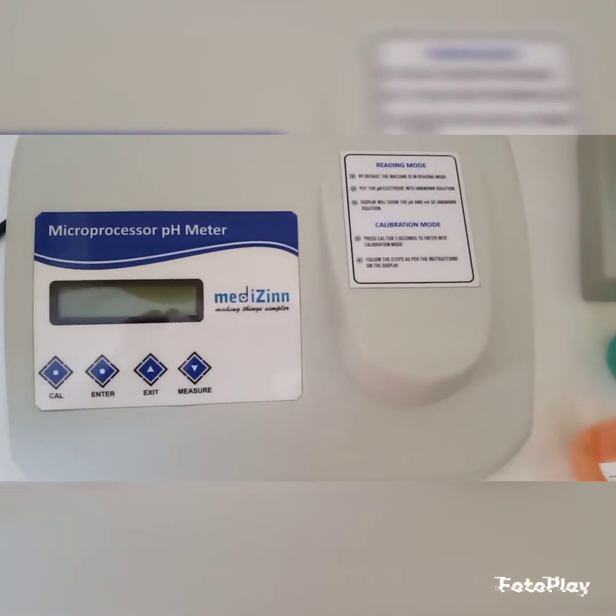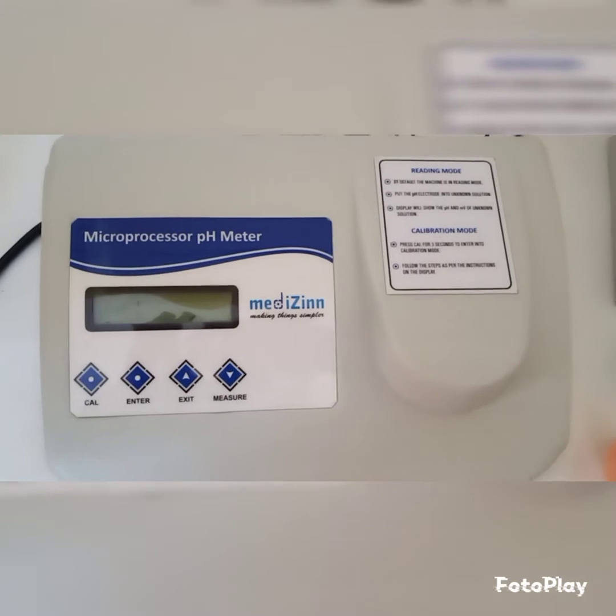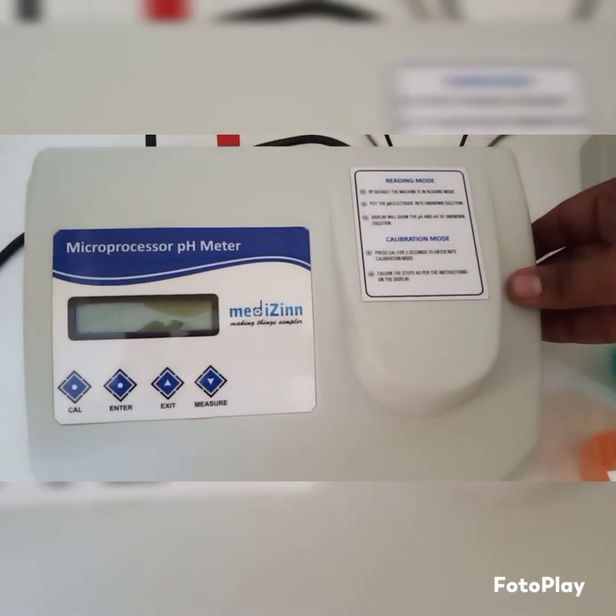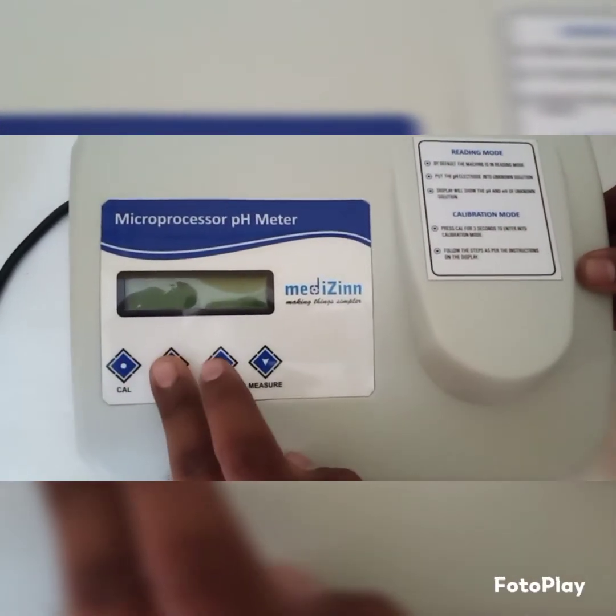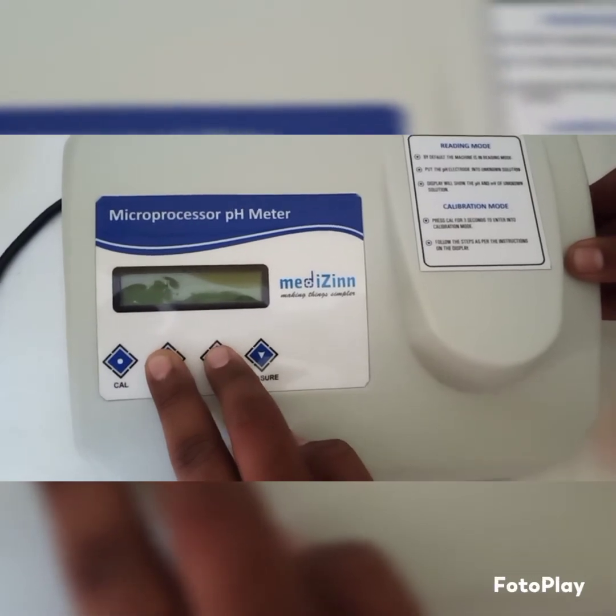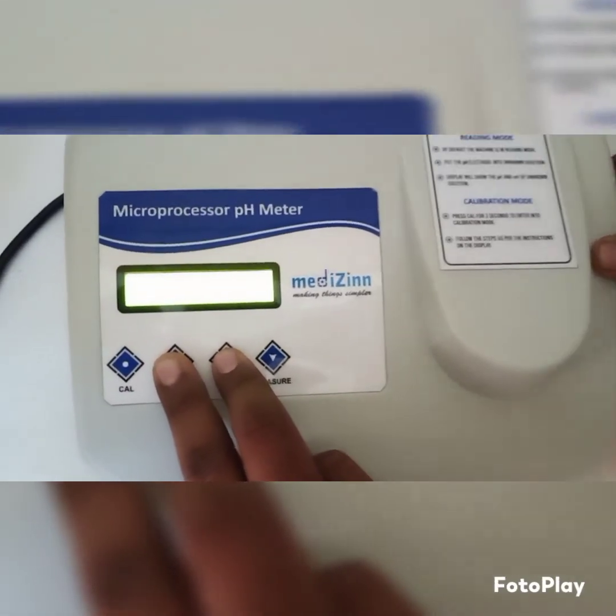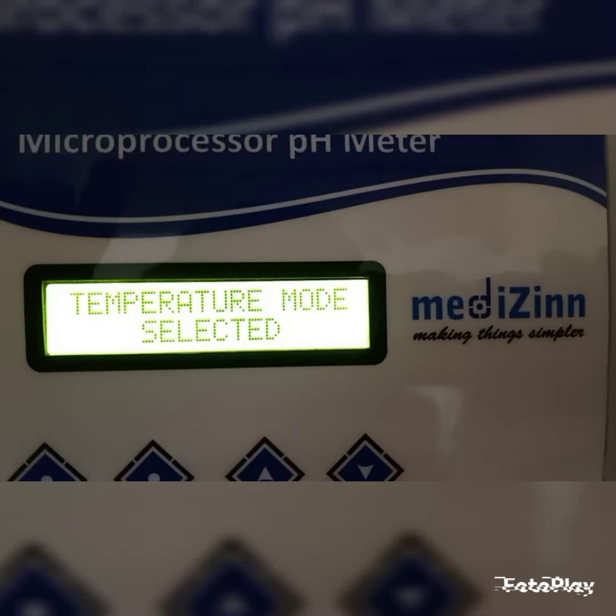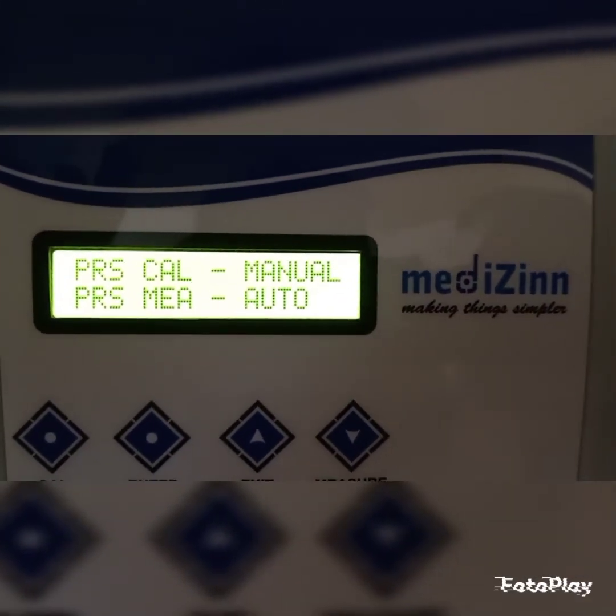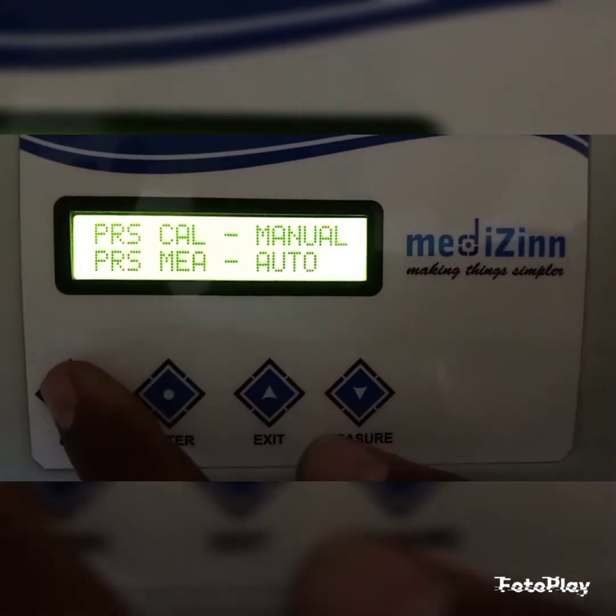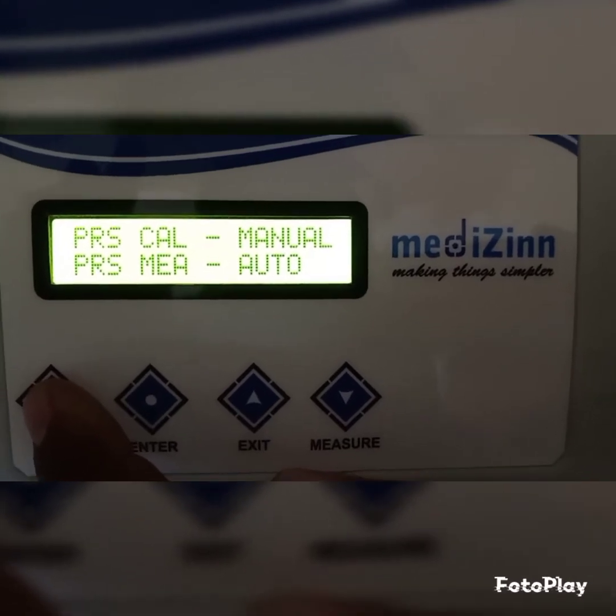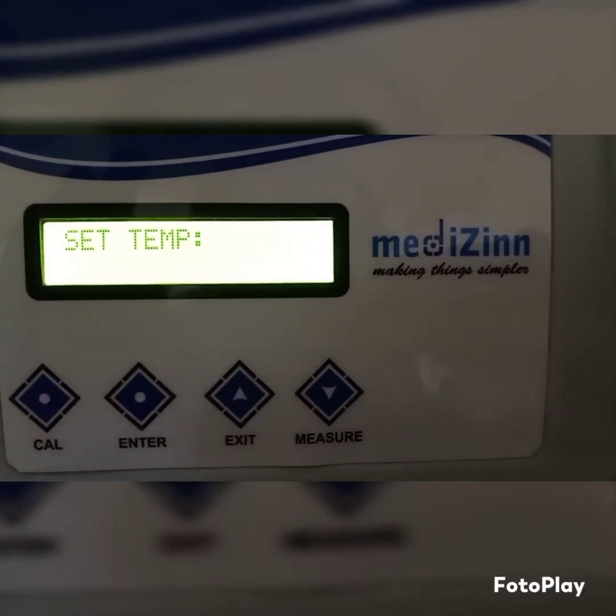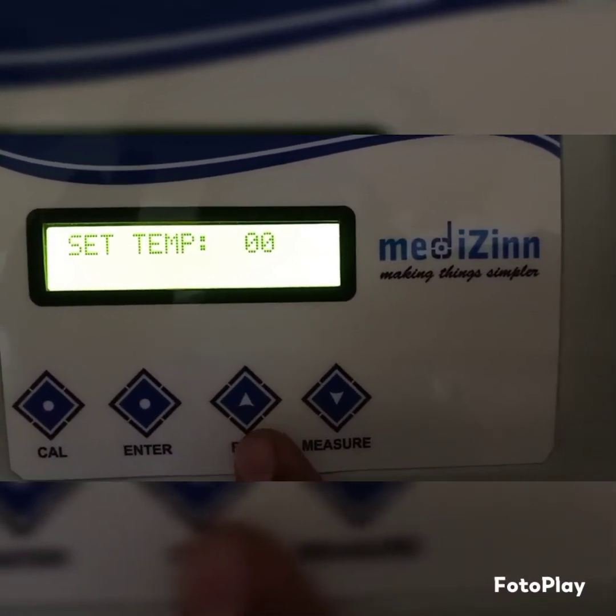Now how to change automatic temperature into manual mode? For that, switch off the machine, press second button and switch on the machine, and then press third button. Temperature mode selected. Press cal for manual and measure for automatic temperature compensation. So suppose we want to go for manual temperature.